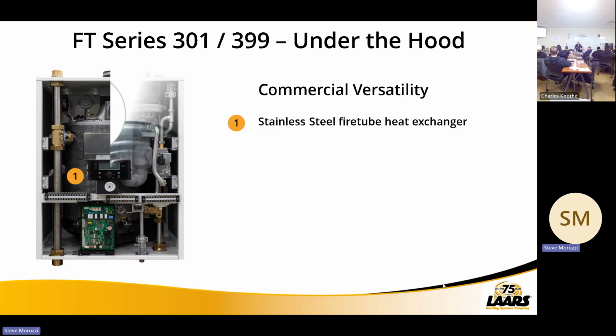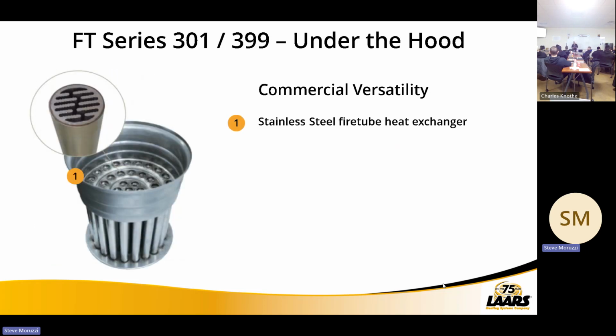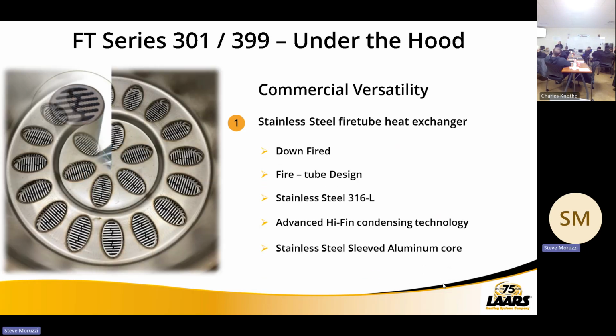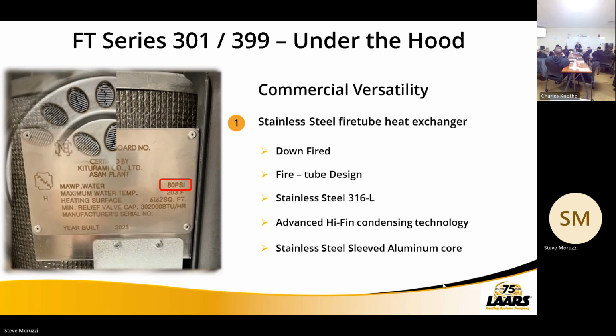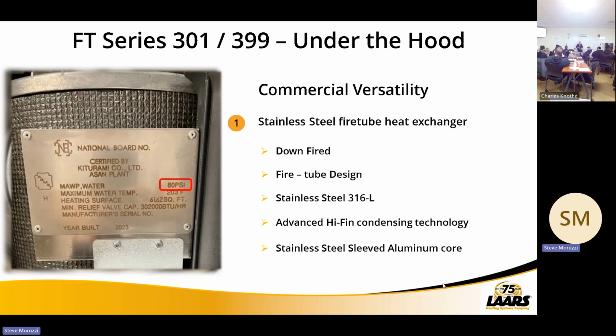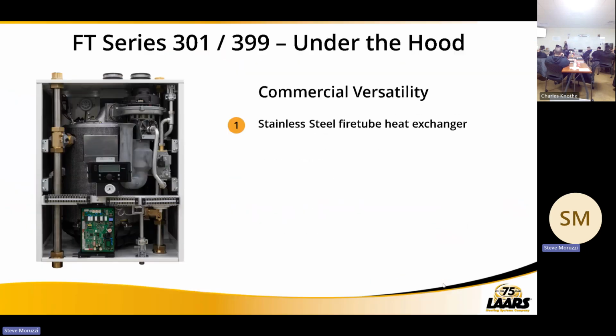So again, stainless steel fire tube heat exchanger. There is no indirect tank in this. This is heat only. And there is the stainless steel. I'm showing the residential models. And this is the commercial model as well. All right. So again, we still use the aluminum sleeve or aluminum core for the advanced high fin technology to transfer that heat to the flue gas to the stainless. 80 psi on the heat exchanger rating, by the way.